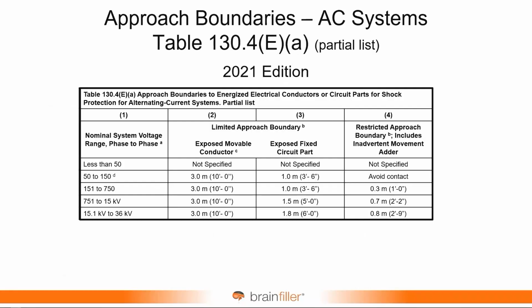Let me explain what's going on here. So this was the table as we knew it for 2021. This is an excerpt of it. And if you look under the limited approach boundary, the exposed movable conductor, you see there was 10 feet, and then the metric was 3 meters. Well, it turns out 10 feet is actually 3.048 meters. And you might think, so we're addressing rounding. That's correct rounding. 3.048, if you round it properly, it would be 3 meters. Well, yes, mathematically that's true, but it introduced a bit of a problem.